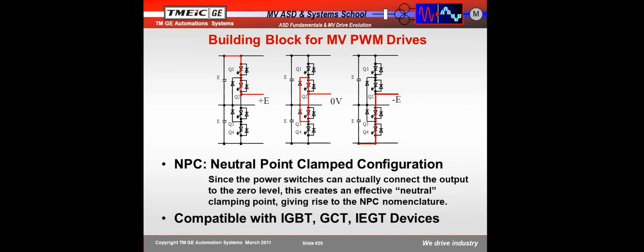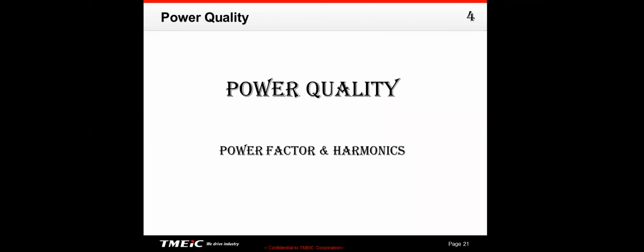Well, when you get into medium voltage motors, there is no such thing. You don't have regular motors and VFD rated motors. They're just medium voltage motors. And so it becomes more important than ever to make sure and to control those voltage spikes. Fortunately, manufacturers of medium voltage drives have responded to that, and the output waveforms are much better on a medium voltage drive than they are on a low voltage drive, which I will show you coming up.